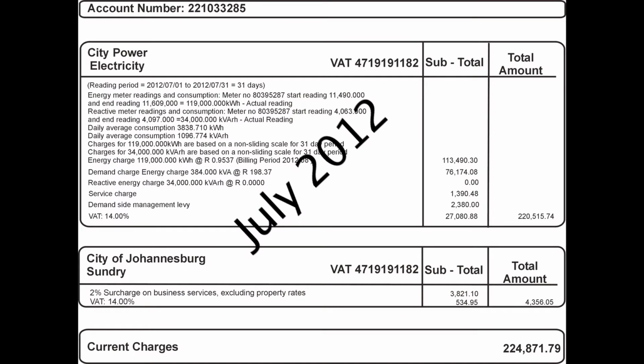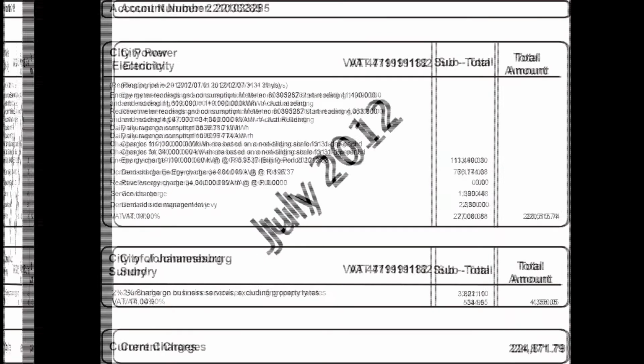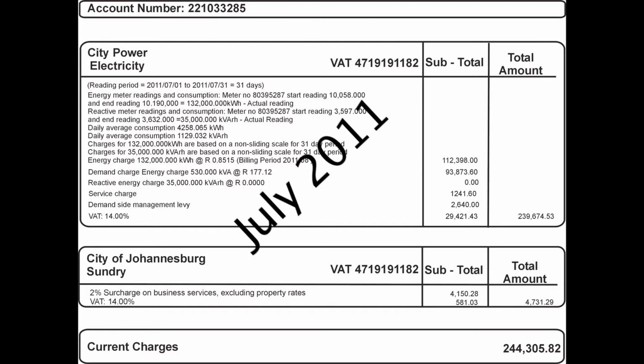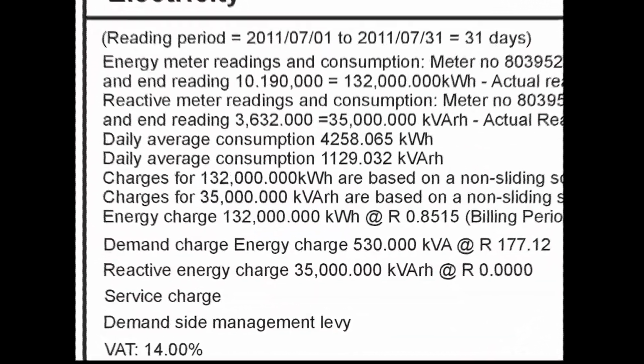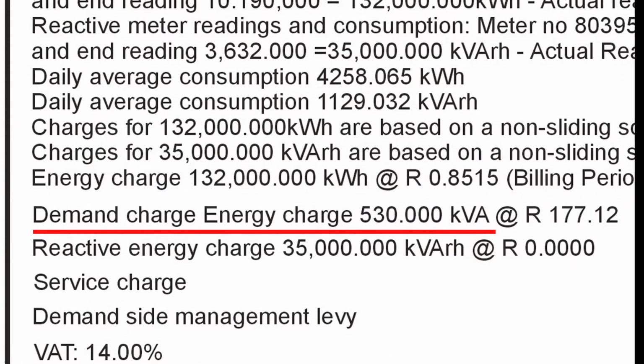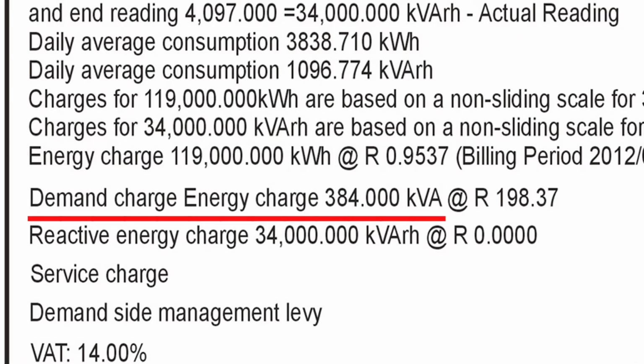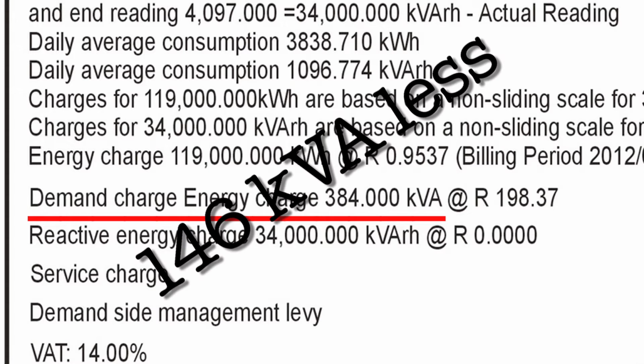You could, however, correctly argue that these are our calculations and the proof of the pudding is in the eating, and in this instance the pudding is the electricity bill. Here is a comparison between the July 2012 and July 2011 bill, which was prior to the PowerGuard installation. In 2011, the bill indicated a peak reading of 530 kVA during that month, which incidentally was the reading we used for our calculations. Compare that to the 2012 bill, and we notice a peak reading of 384 kVA, a difference of 146. That's even better than our predicted saving of 130 kVA.